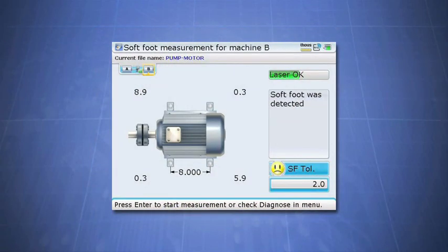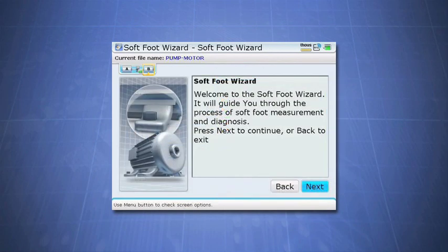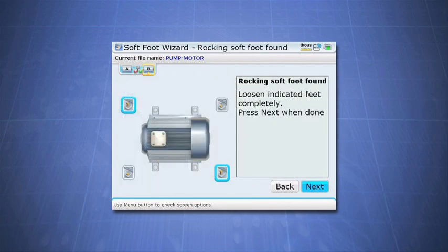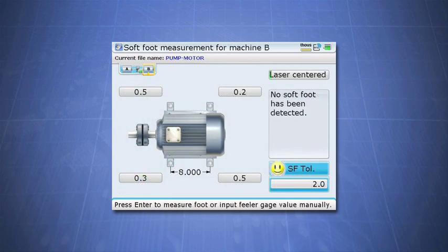So what if you don't have years of experience with softfoot? Before you gain enough experience to diagnose on your own, the Rotalign Ultra's soft foot wizard will help you. The softfoot wizard is your highly experienced field companion that walks you through the process step by step, guiding you graphically through the most efficient techniques of softfoot correction. The softfoot wizard diagnoses your problem and solves it with instructions that are very clear and easy to understand at all experience levels. Once you complete the softfoot wizard, the final value should be less than two mils, which means the softfoot has been removed. With this taken care of, you can now finish the rest of the alignment.